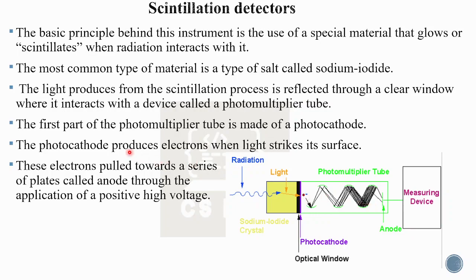The first part of the photomultiplier tube is the photocathode. The photocathode produces electrons when light strikes its surface. This light enters through the optical window in the photomultiplier tube, strikes the photocathode, and generates electrons. These electrons are then directed through a series of plates called anodes, and a positive voltage is applied to the anodes.